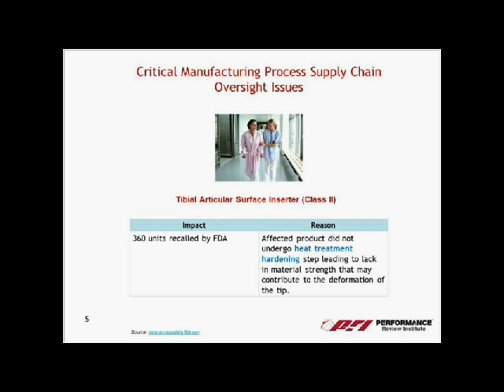This one is a tibial articular surface insert, a Class 2 device, 360 units recalled. The defect identified was either not heat treating to induce hardness in the tip, or performing the wrong process, resulting in deformation of the tip because it wasn't done properly.